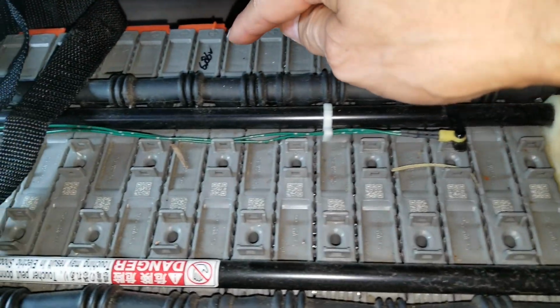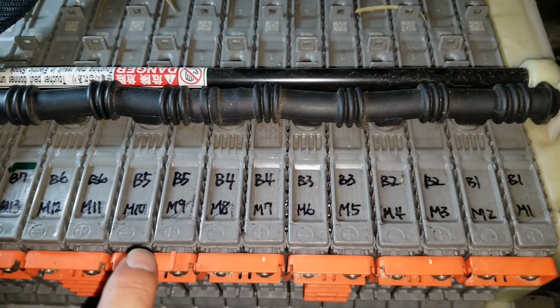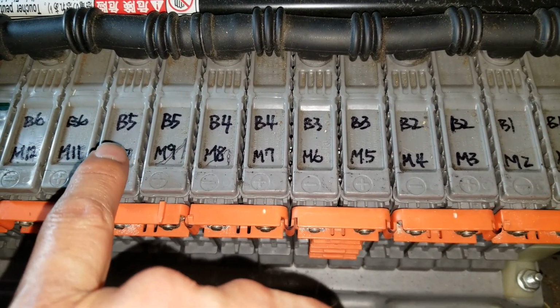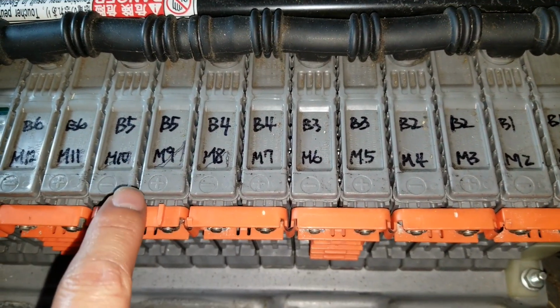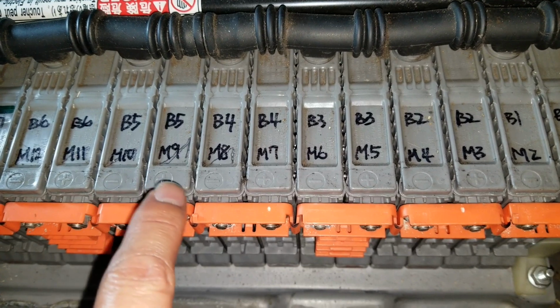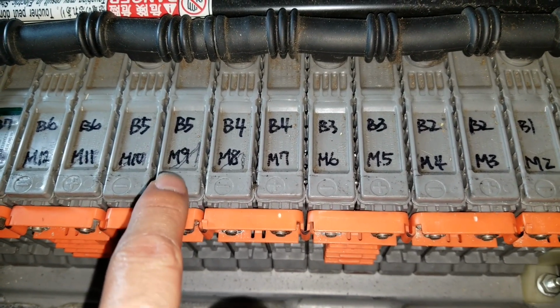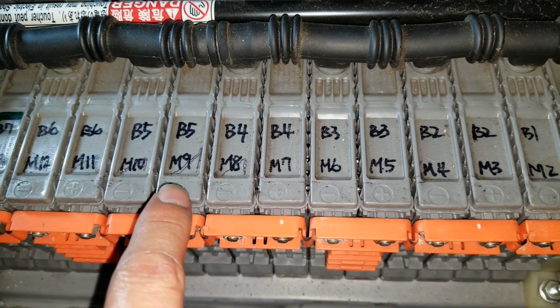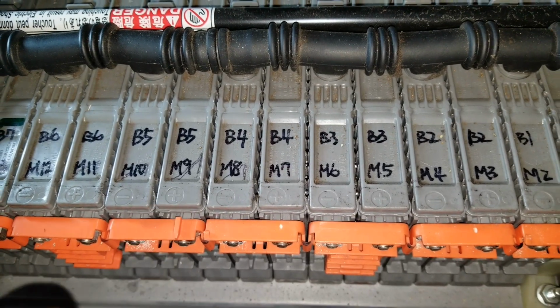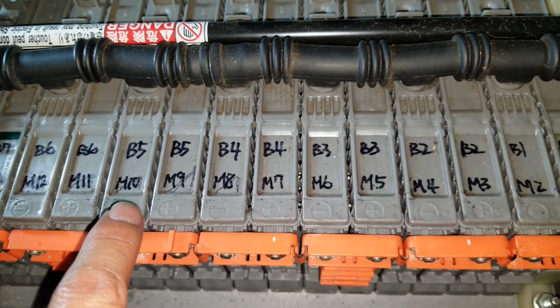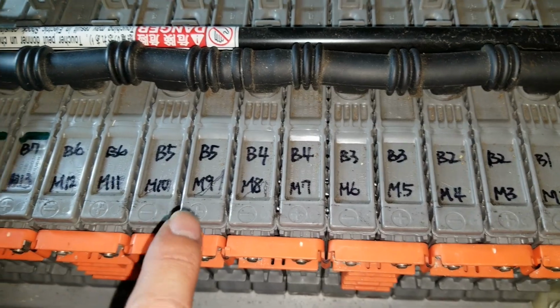So I need to watch this one. See, like I told you, it shows block 5 is bad, so you gotta identify which module is bad. M9 is good because that's like 8.10 volts, and M10 is 6.86 volts. So I'm gonna continue to measure all the voltage.